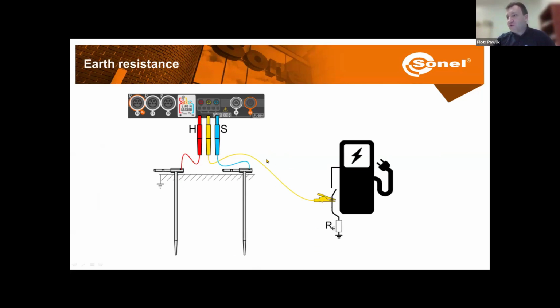So this will be the current measuring circuit. Closer one, S, this is the voltage rod. So this will be the voltage measuring circuit. And then voltage over current will give us the value of resistance. Of course, we can use also other methods like 4-pole, 3-pole with clamps, or 2 clamps method. And in case the charging stations are in the garage, in some building, then we just need to make sure that the earth channel of the charging station is connected to the earthing of the building.